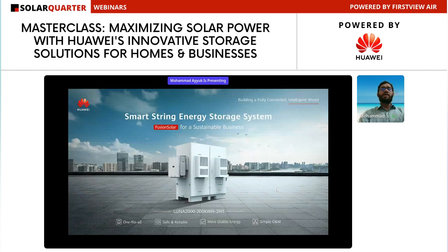This is our C&I energy storage system. As you can see on the screen, this is a 200 kilowatt hour, 100 kilowatt system. This is a cabinet model system, contrary to our utility solution which is a container solution. But all the components like PCS, smart rack, auto controller, everything is embedded in the system itself, which reflects in the lower balance of plant cost.